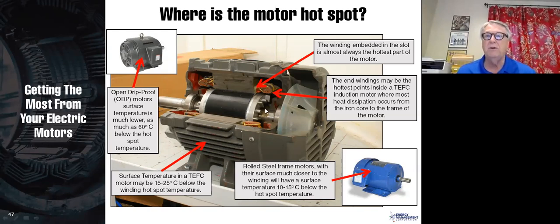Now, most really good quality industrial motors are totally enclosed fan cooled. And in this case, the motor may be 15 to 25 degrees below the winding hotspot temperature. So again, we can take our infrared gun, we can measure the temperature of the frame, add 25 degrees to that, and that's a pretty good indication of what our hotspot temperature is inside of the motor. So I think that's good information to know.